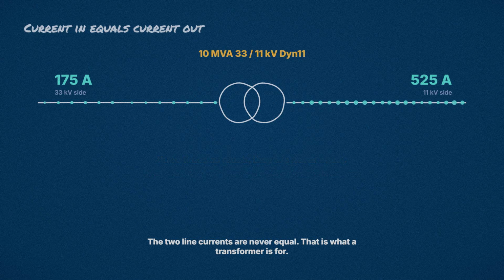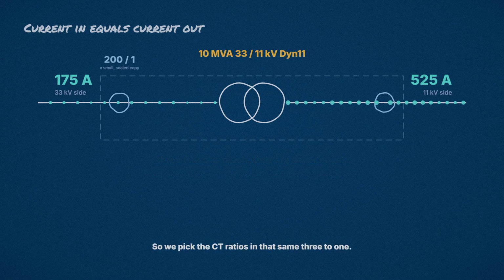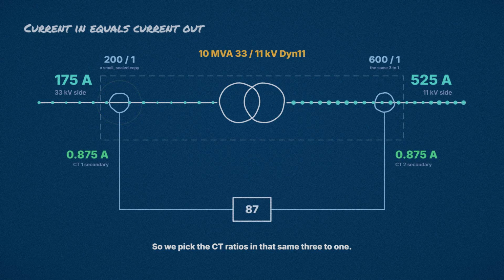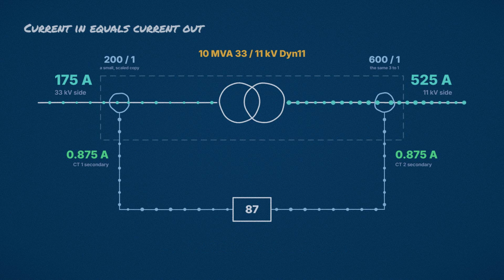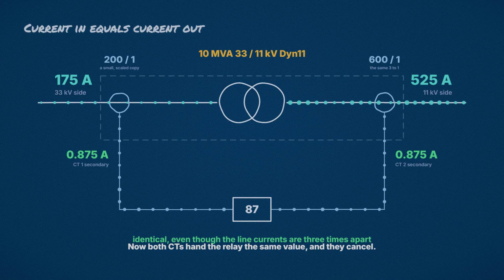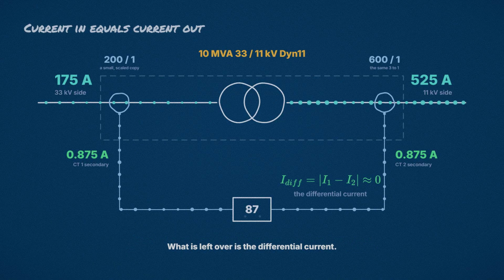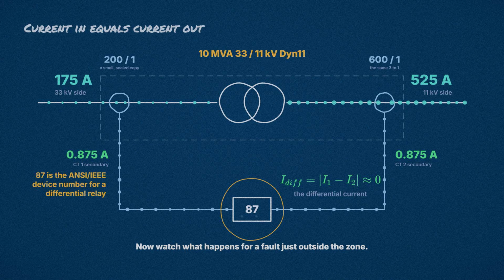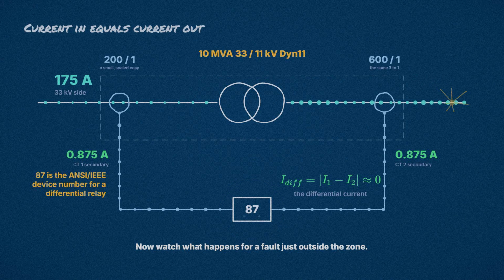A current transformer is a device that makes a small, scaled copy of the large primary current. 200:1 on the high side, 600:1 on the low side. Now both of them hand the relay the same value. Those two copies meet at the relay and they cancel. What is left over is called the differential current, and in a healthy transformer it is almost nothing. The relay that measures it carries device number 87, the ANSI standard code for a differential relay. Now watch what happens when a fault appears just outside the zone.